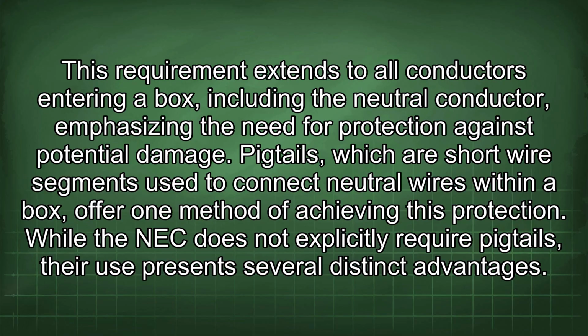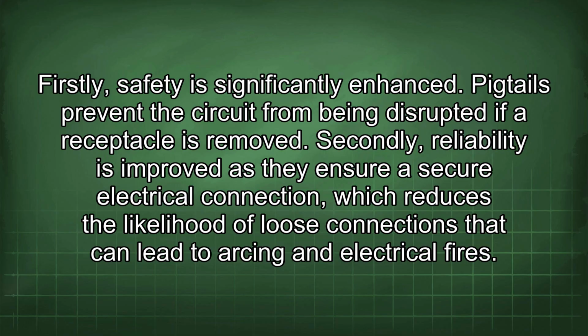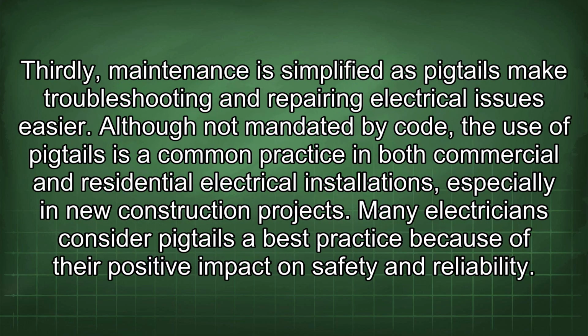damage. Pigtails, which are short wire segments used to connect neutral wires within a box, offer one method of achieving this protection. While the NEC does not explicitly require pigtails, their use presents several distinct advantages. Firstly, safety is significantly enhanced. Pigtails prevent the circuit from being disrupted if a receptacle is removed. Secondly, reliability is improved as they ensure a secure electrical connection, which reduces the likelihood of loose connections that can lead to arcing and electrical fires. Thirdly, maintenance is simplified as pigtails make troubleshooting and repairing electrical issues easier.